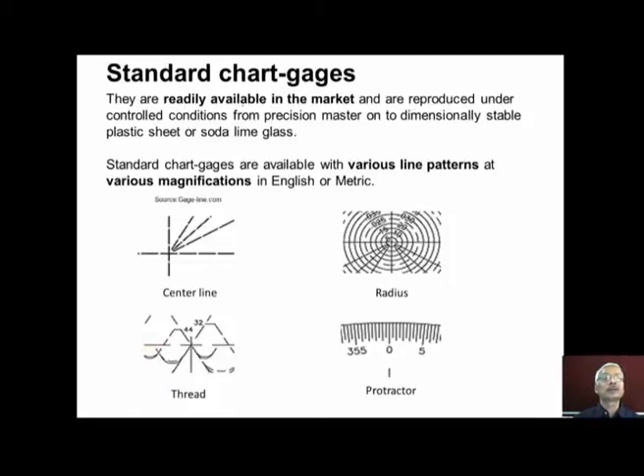Commercially standard chart gauges are available in the market and they are reproduced under controlled conditions from a precision master on a dimensionally stable plastic sheet or soda lime glass. Standard chart gauges are available in various line patterns at various magnifications like 10x, 20x, 50x. So chart gauges with different magnifications are available in English as well as metric units.